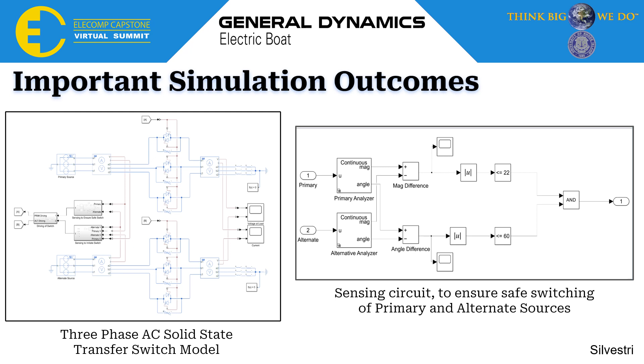On the right is one of the sensing circuits. This circuit monitored magnitude and phase angle of the two sources and ensured that when switching from the primary to the alternative source, everything was within a certain range, in order to stop current rush and avoid frying some of the sensitive components down the line.